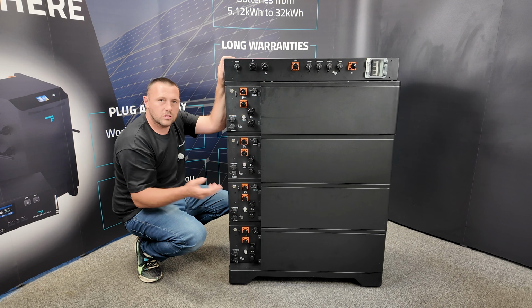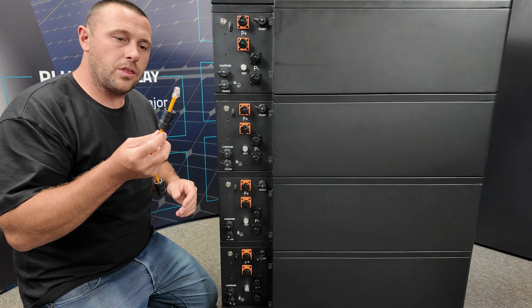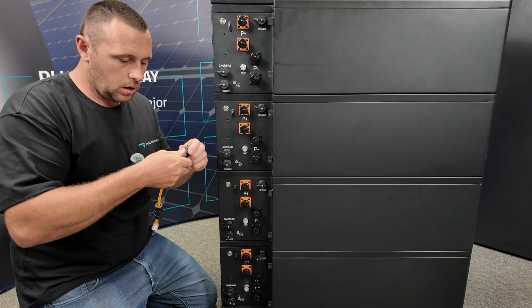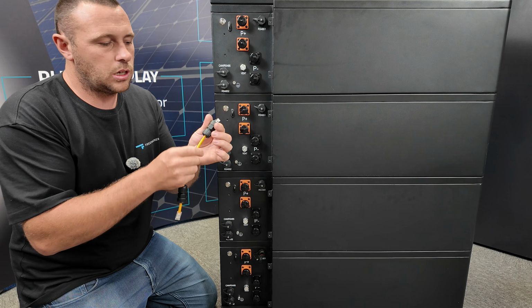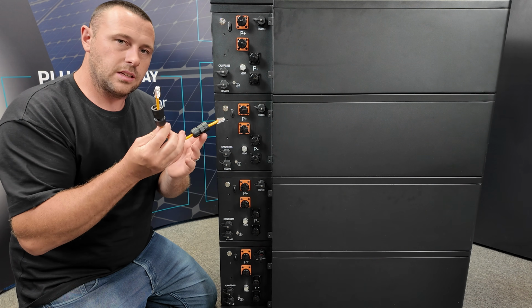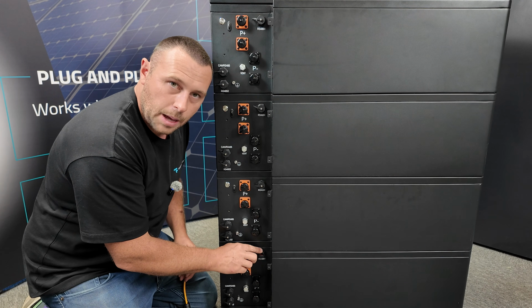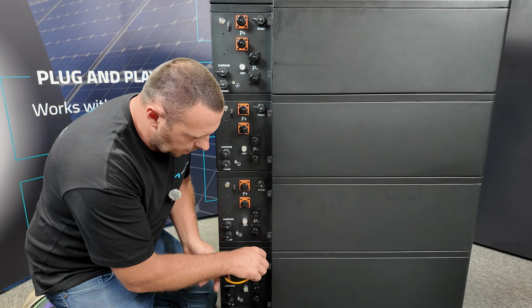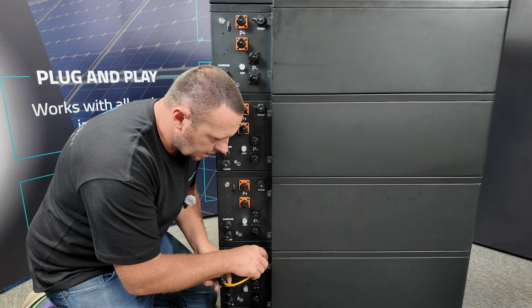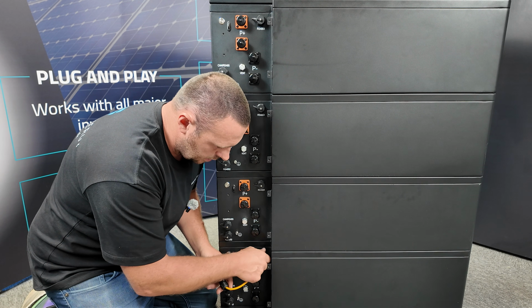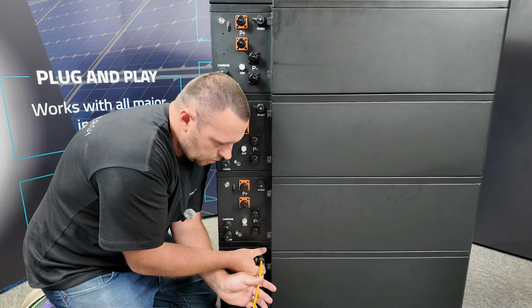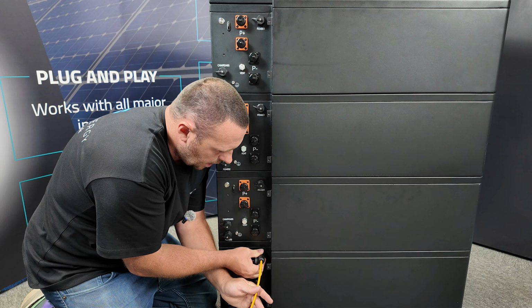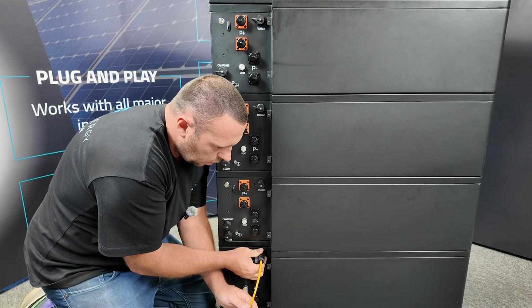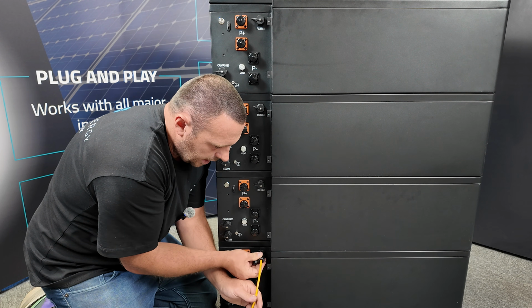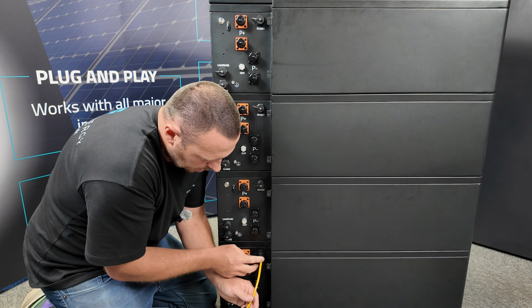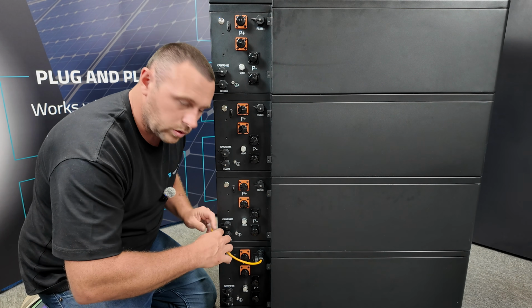Now I've spoken about all of the ports, let's actually get them wired up. To start the wiring, we're going to start with the CAN communication leads. These are the short ones that are module to module communication. Do yourself a favour by just loosening that gland a little bit, sliding these back, just makes the initial installation a bit easier. You'll want to remove the cap from the RS485-1 port here, plug in that communication lead, slide the gland back over, and then securely fasten, making sure that the cable stays still so you don't kink that cable and potentially damage the wires. Once you've threaded the collar on nice and tight, you can then do up the gland. Again, just finger tight is plenty for this, but just want to make sure that communication port is watertight.